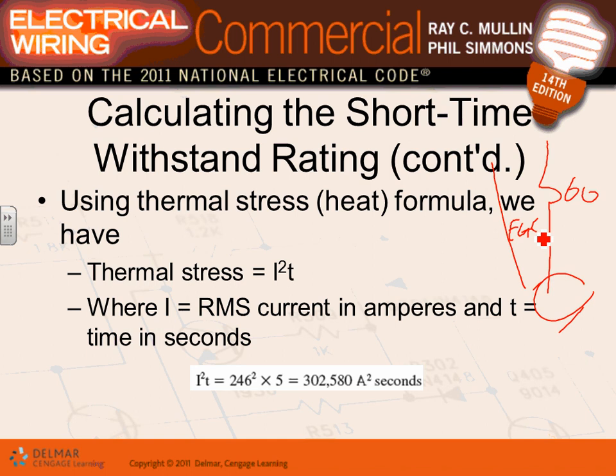I did a ground fault here. The ground fault current, guys, is 246 amps. I came up with 246 amps. Now the question would be, I measured it, I came up with 246 amp ground fault. How much heat will this generate in the conductor?